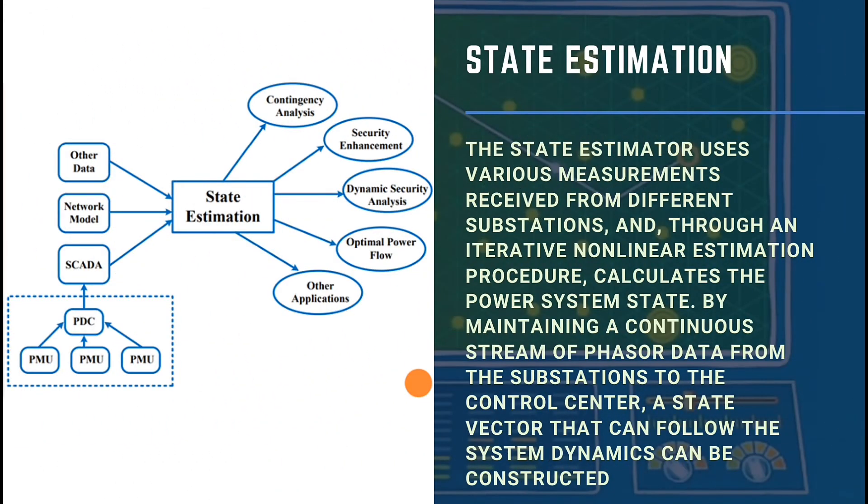State estimation: The state estimator uses various measurements received from different substations, and through an iterative nonlinear estimation procedure, calculates the power system state. By maintaining a continuous stream of phasor data from the substations to the control center, a state vector that can follow the system dynamics can be constructed. For the first time in history, synchronized phasor measurements have made possible the direct observation of system oscillations following system disturbances.